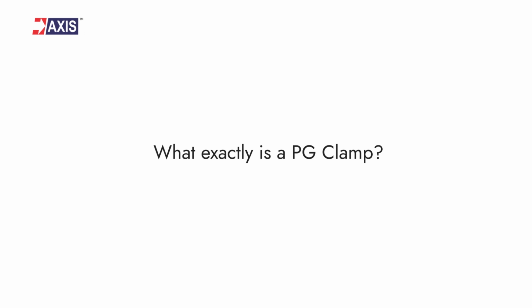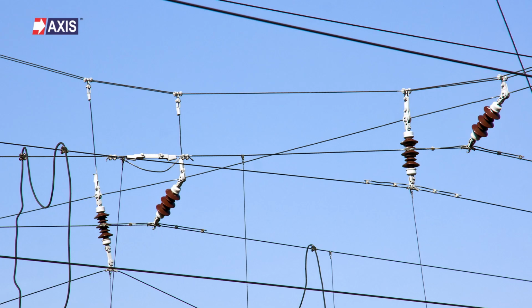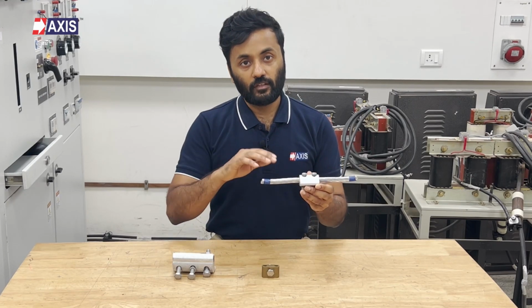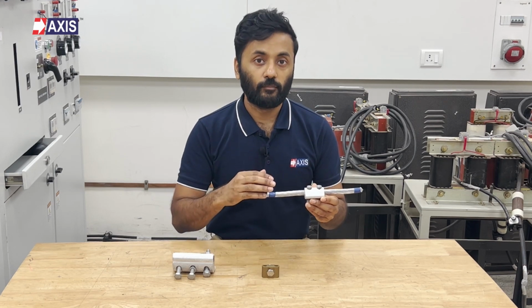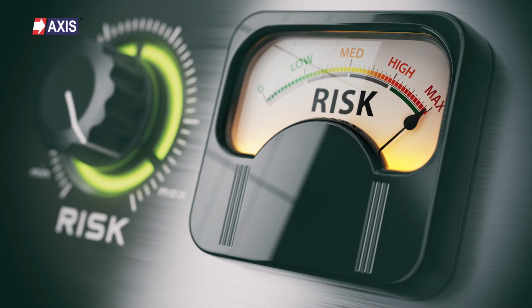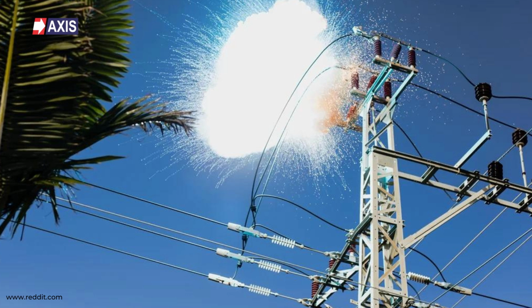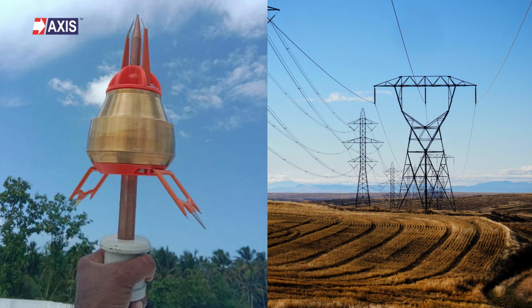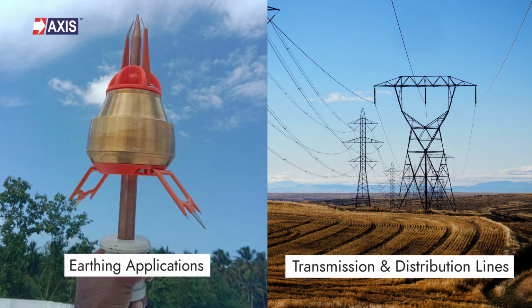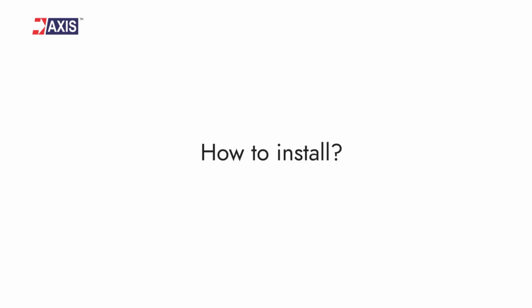Now let's understand what exactly a PG clamp is. PG clamps are used to connect two or more conductors whose axes are parallel to each other. PG clamps are designed and installed to ensure that the conductors don't come in direct contact with each other. When conductors are connected directly without a proper connecting mechanism, there will be increased electrical resistance at the contact points. This results in heat buildup and energy loss. Hence, to avoid such harmful electrical discharge in earthing applications, in distribution and in transmission lines, a PG clamp is crucial. Let's briefly understand how this clamp is installed.